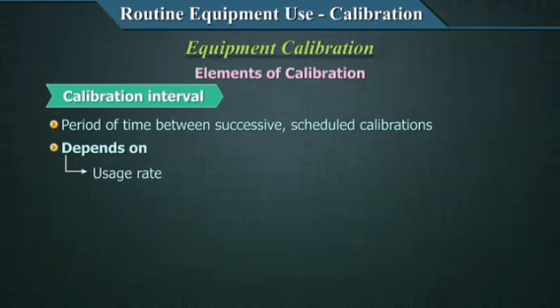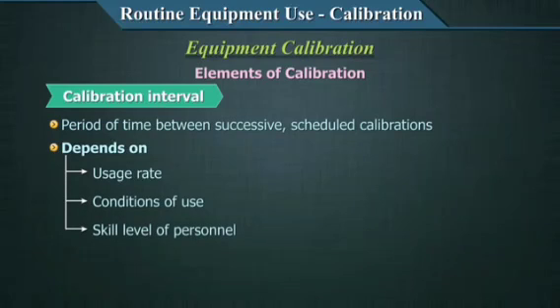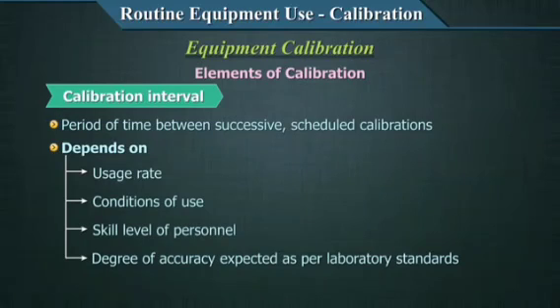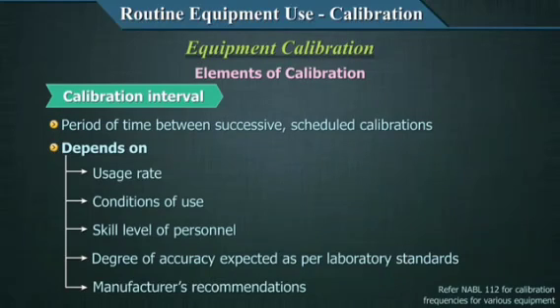This depends upon the usage rates, conditions of use, skill level of the personnel using the equipment, degree of accuracy expected as per your laboratory requirements, and the manufacturer's recommendations. You can get some idea of what the frequencies of calibration are if you refer to NABL 112. It's a free download document. It's a document of NABL, which is an accrediting agency for laboratories, and have specified certain durations when calibrations are warranted. But then the final decision, if you want to calibrate more often, is yours. If you feel that your equipment is being used excessively and requires verification on a more frequent basis, it's entirely up to you to do that.